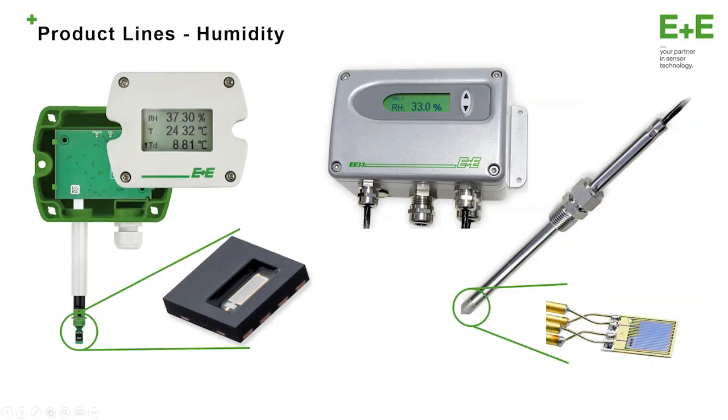And it also allows us to run a heavy amount of current through. So if there's been oversaturation of the sensor, let's say it has gotten wet or chemicals have been absorbed into it, we'll heat this portion to about 250 Celsius to burn off any excess chemicals or moisture. That clears out those cracks and crevices embedded into the silicon that we produced, and allows it to dry out. As it returns to a normal temperature, it starts to absorb moisture again and gives you an accurate reading. The reason we have two sensors in some cases is because once you heat this up, you can't get an accurate humidity reading. So we have a separate temperature sensor placed a distance away so it's not impacted by that.